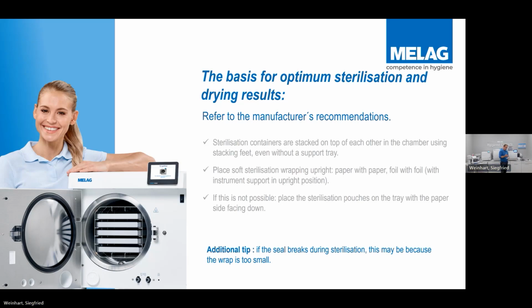Now, if we overload this pouch, when that pouch is in the sterilizer, okay, paper side down, the steam will come in. That pouch is going to want to breathe. It's very similar to putting a bowl in the microwave with cling film on the top of the bowl. As soon as that microwave turns on, what happens, if you look through, is the cling film tries to expand, so it gets bigger and bigger. And that's what's happening inside here with the pouch. So the instrument is inside. This instrument is perfect for this pouch. So the instrument is inside, steam comes in, that pouch will want to breathe.